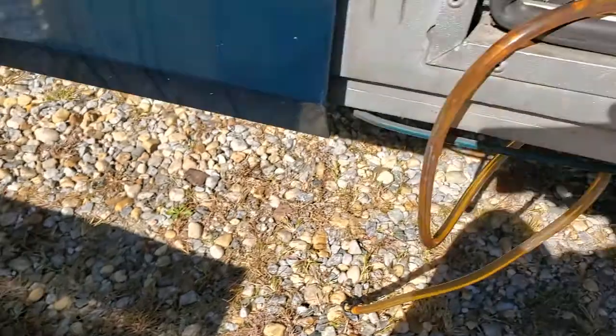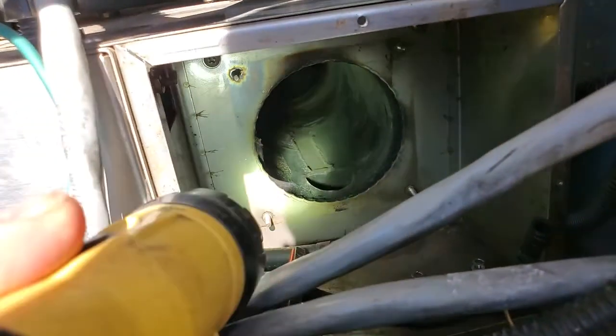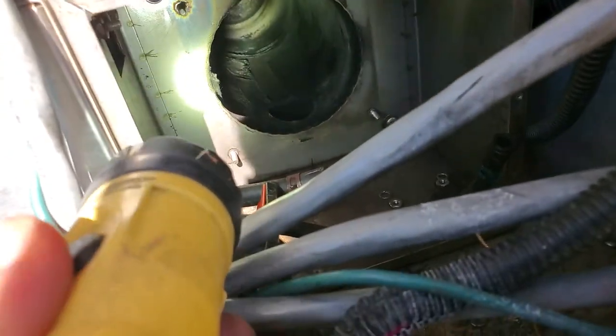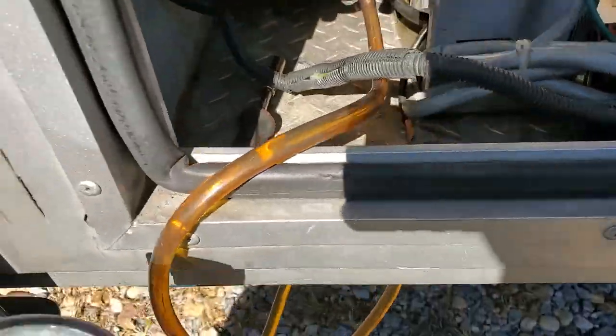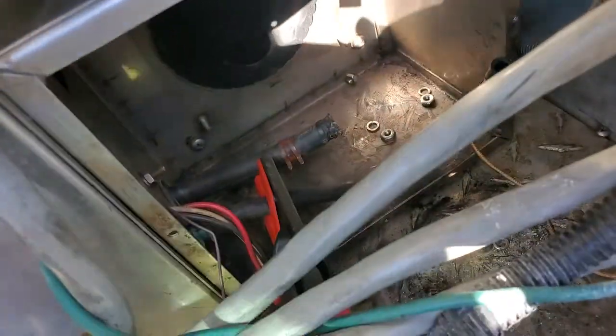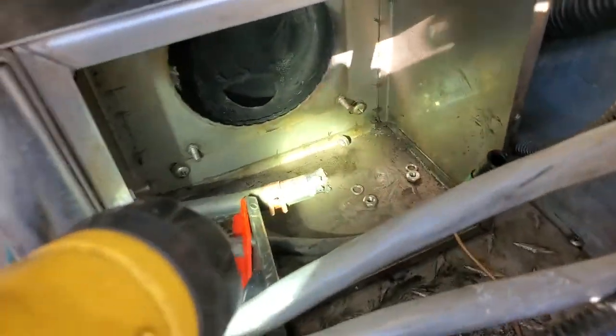That was the teardown of that. Now I'm going to get in there and clean that hole out a little bit. That's what you want to look for — you're looking for cracks, anything getting moist. Sometimes they'll crack and they'll leak down in here. I've got my air bleed. Notice I pinched off the fuel hose with special pinchers — it won't cut them. The big hose is air, and then another one's fuel — diesel.